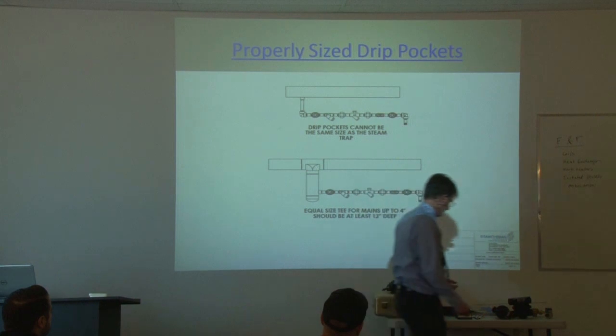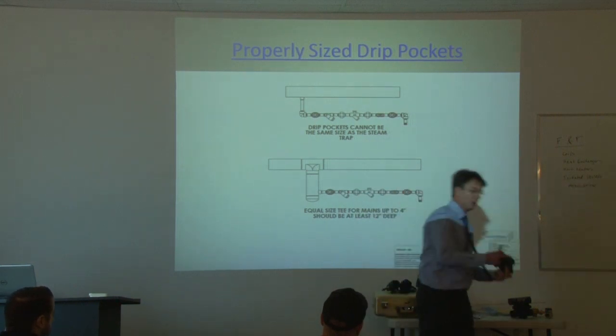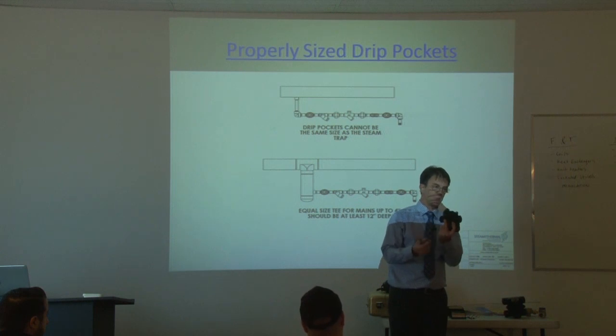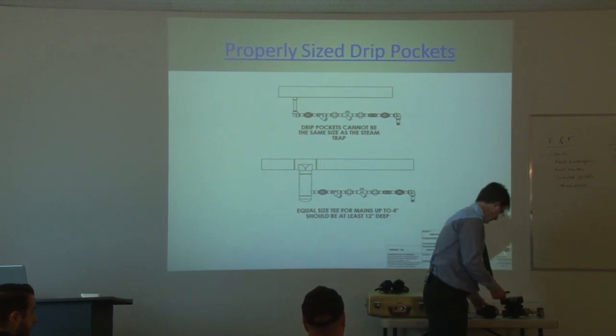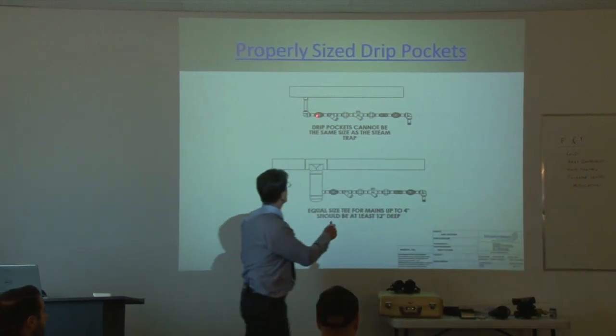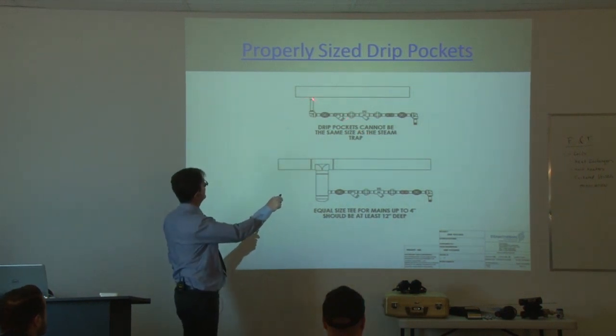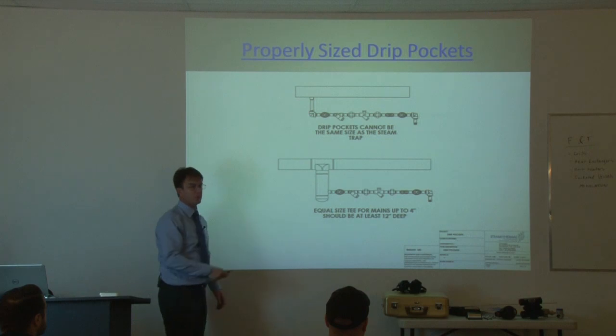Now, a lot of times, if somebody is not familiar with steam traps or steam systems, they'll take a three-quarter inch trap or a half-inch trap and say, well, it's three-quarter inch. I'll just put three-quarter inch pipe on that side and put a three-quarter inch pipe here, make a little tapping here, and then just three-quarter inch all the way.